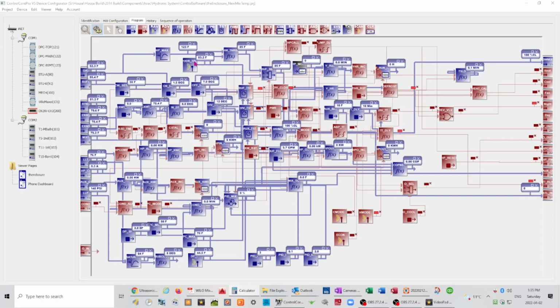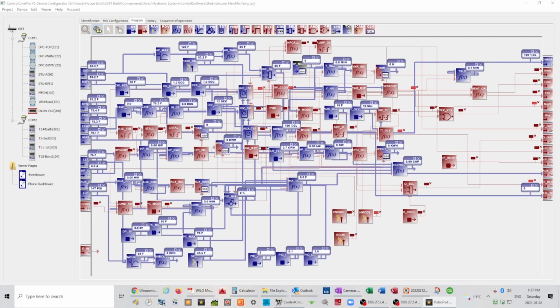So the heat pump will activate when the buffer tank temperature is equal to our panel target temperature plus 2 less 1.5 degrees, and turn off when it is our target panel temperature plus 7 degrees. And what that allows is for the heat pump to run for a reasonable amount of time and then shut off and not have to run for, in our case, several hours based on current outdoor temperatures. So you don't have any type of short cycling of the heat pump. The heat pumps become more efficient, just like a boiler. The longer they run, the more efficient they become. They're less efficient on startup and shutdown. So that's just one given example of the functionality and the complexity of the system that you can program.